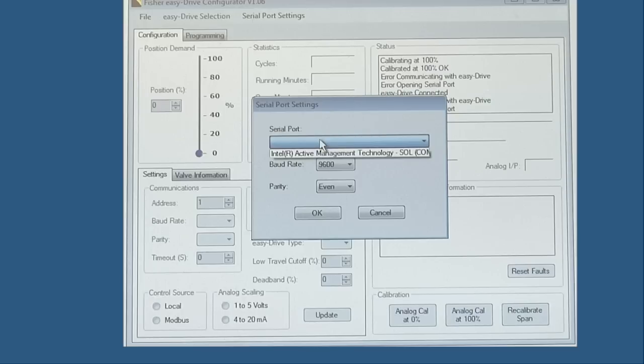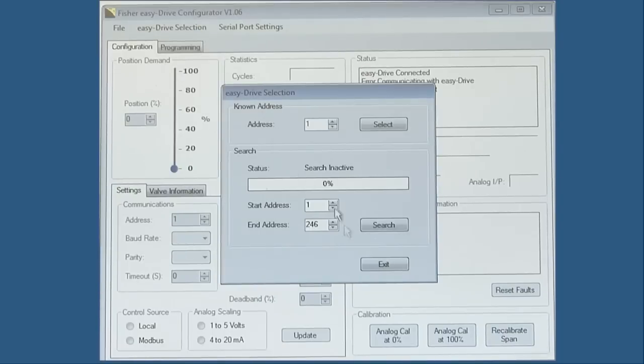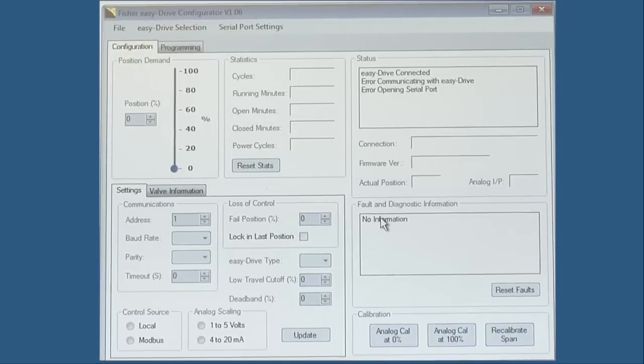Once that has been completed, use the correct baud rate for your device. Ours is 9600 and at an even parity. If the EZ-Drive is not connected, then go to EZ-Drive selection within the menu bar and search for the EZ-Drive. If the EZ-Drive is not found, please contact your local Emerson sales office.